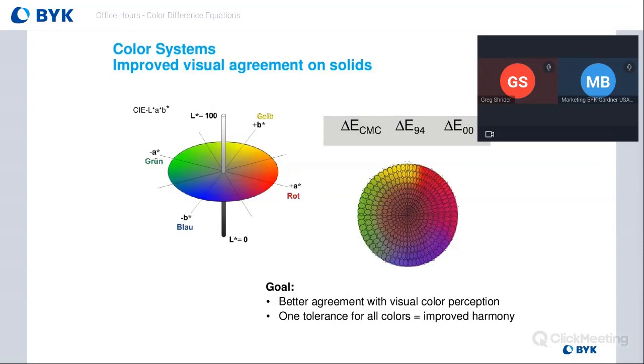So technically it's directional, it's not diffuse, because all of your multi-angle color measurement devices are directional. And that means if you measure it one way and then turn it 90 degrees, if the sample is directional, you'll get different numbers.